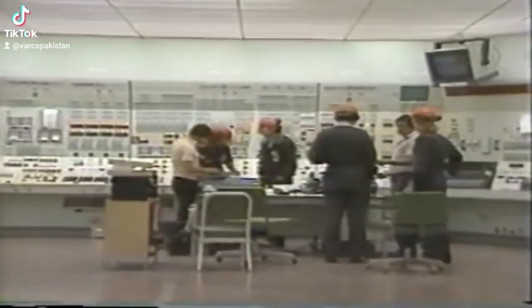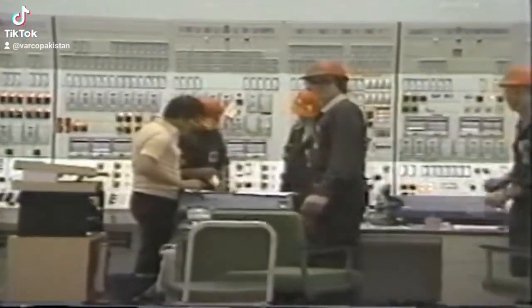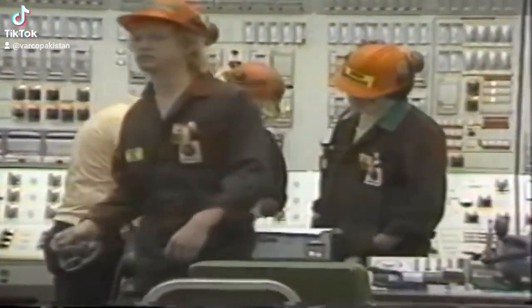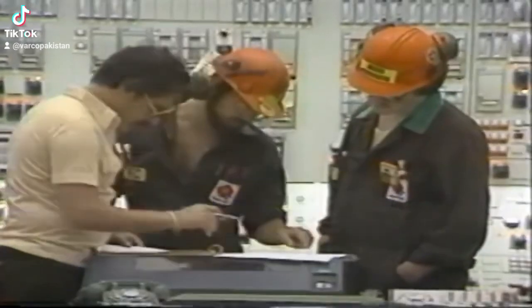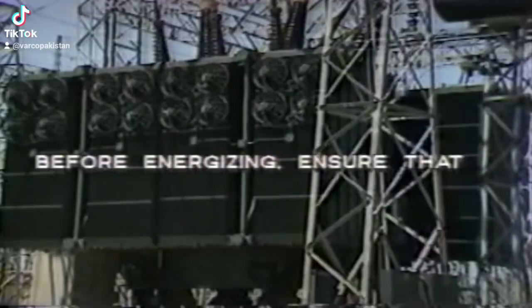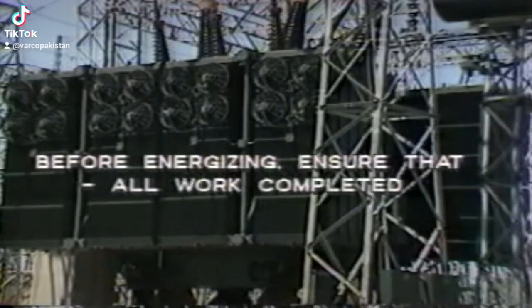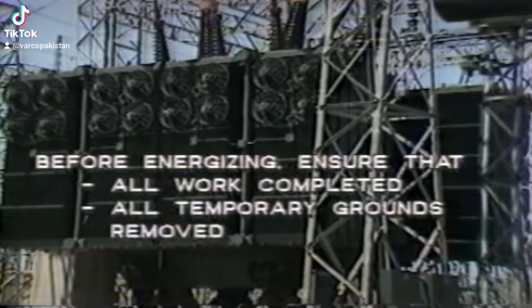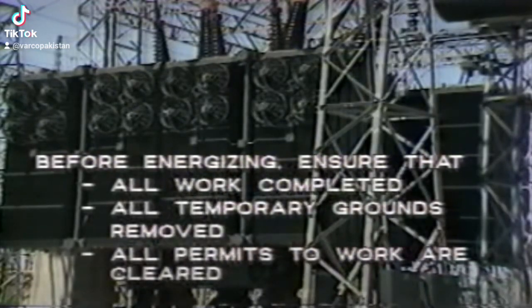The purpose of in-service tests is to check the protection schemes under operating conditions, and that is with the primary equipment energized and on load. Energizing the primary equipment is usually the responsibility of one designated commissioning engineer, assisted by the operating personnel, the protection personnel, and other departments. Before energizing, they will make sure that all work has been completed, that all temporary grounds are removed, and that all permits to work are cleared.